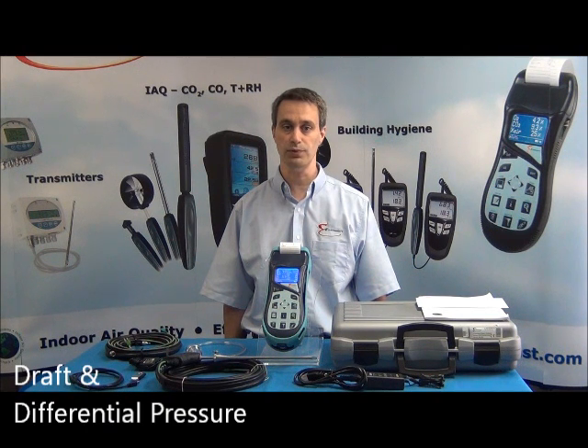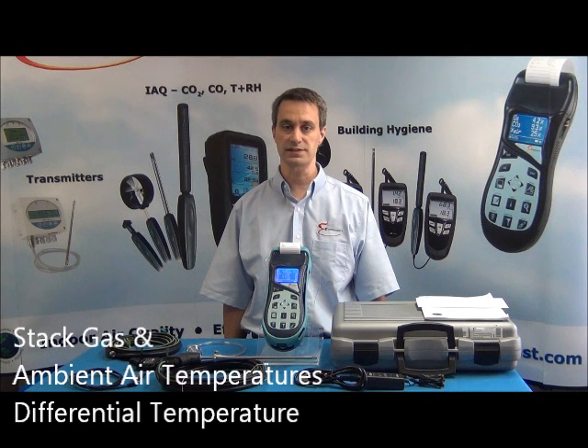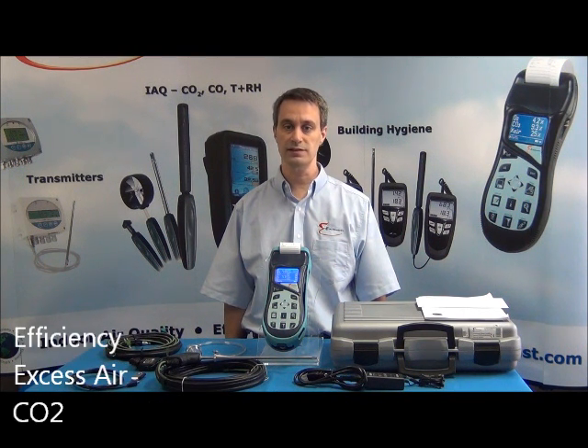The E4400 has a pressure sensor that allows for measurements of draft and differential pressure. It also has a 2-channel thermometer for measurements of stack gas and ambient air temperatures and calculation of differential temperature. The E4400 calculates efficiency, excess air, and CO2. The E4400 emissions measurements can be corrected for a programmable oxygen reference level.